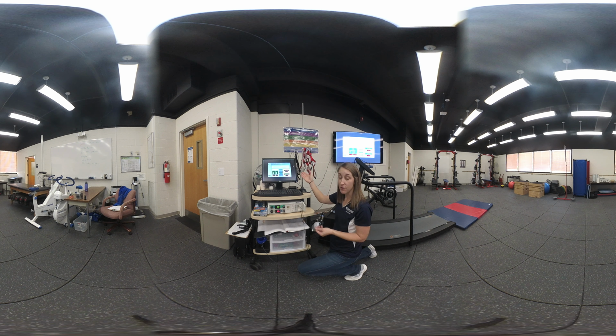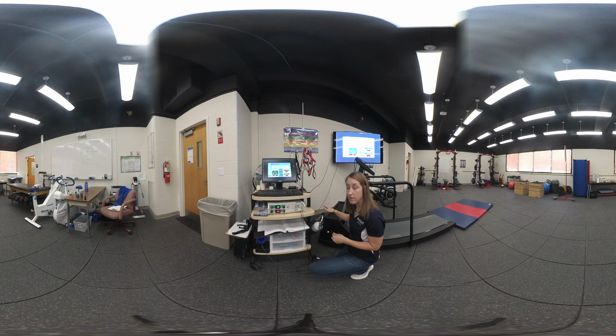So on our machine, it specifically gives us a smiley face. You might have a check or a thumbs up saying, yep, that part of the calibration was successful. For the next part of the calibration, we don't want to collect room air. Instead, we want to collect some sort of gas calibration that we have provided for us.